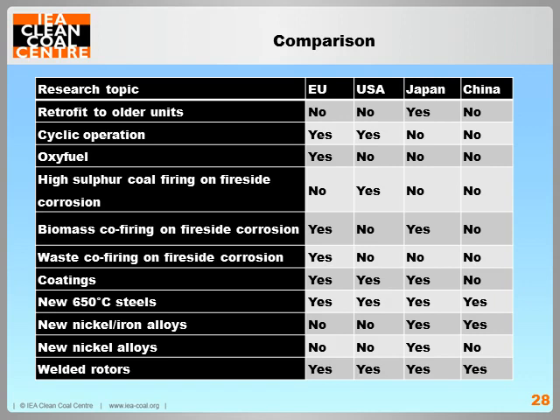Coatings are being assessed in most programs, but with no tangible benefits to date. New steels are under investigation in all parts of the world, with some promising candidates. New nickel alloys and nickel iron alloys have been developed in Asia specifically for AUSC technology. All programs assess welding nickel alloys to ferritic steels to manufacture the steam turbine rotor in order to reduce capital costs.